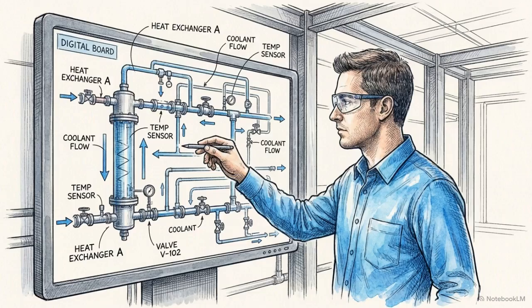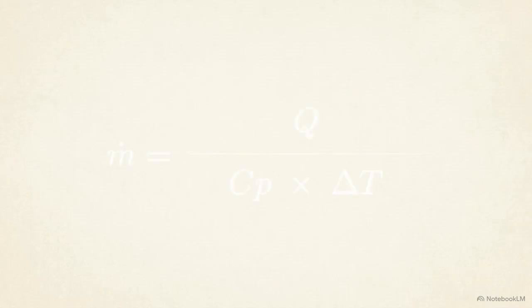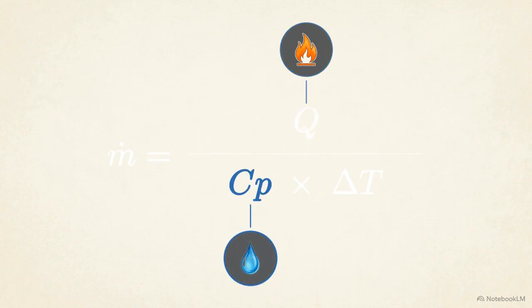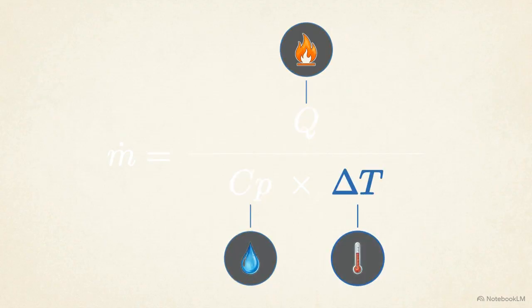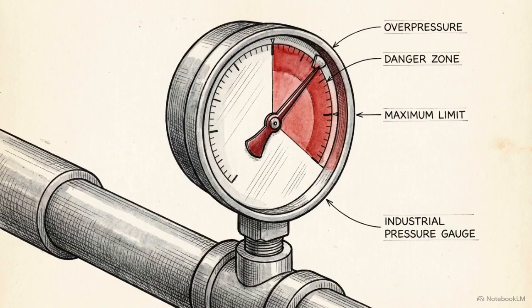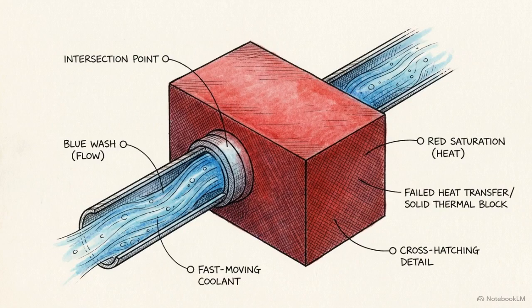To ensure this works, thermal engineers calculate the exact mass flow rate required. They divide the total 15 kilowatt heat load by the specific heat capacity of the chosen coolant and the maximum allowable temperature difference. You cannot simply pump fluid faster to increase cooling. Thermodynamics dictates that once you reach a certain velocity, the fluid passes through the plate too quickly to conduct heat effectively, leading to sharp diminishing returns.